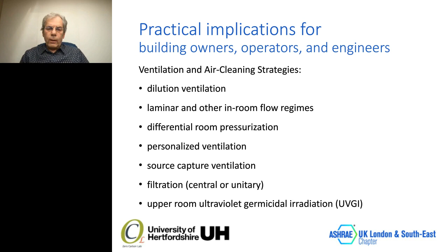ASHRAE position document states that ventilation represents a primary infectious disease control strategy through dilution of room air. And this corresponds directly to the Wells-Riley infection equation that we saw a few slides ago. Also, highly efficient particle filtration is likely to reduce the airborne infectious particles, and directed supply and/or exhaust ventilation is important in several settings, including operating rooms.